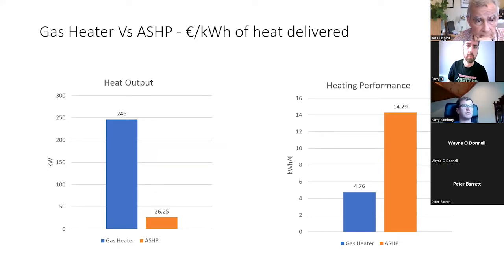When you're looking at a piece of plant that's heating a space, the first thing we looked at was the actual heat output, the ability of this piece of equipment to heat the space. We discovered that the gas heater's fan consumed 10.5 kilowatts of electricity when in use. And when in use, it also consumed 289 kilowatts of gas, assuming 85% efficiency, and you get the two of them together. Total output, should I say, is 246 kilowatts. So that's a phenomenal amount of heat coming out of this device to heat the room. And as a result, it's very, very effective at heating the church very quickly.